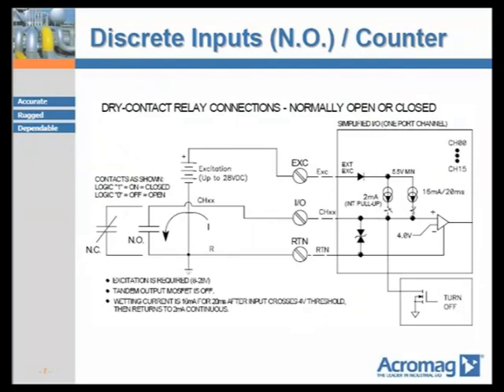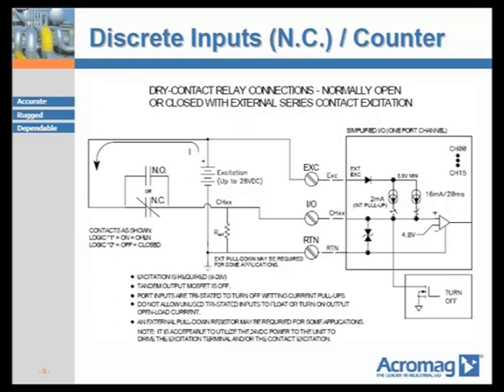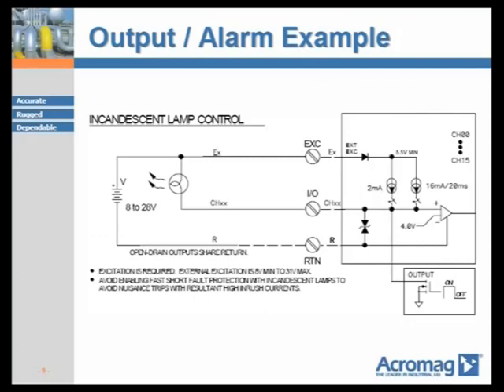This diagram shows the electrical connection to commonly used normally open dry contacts or proximity-type switches. The programmable wetting current sources act like pull-up resistors so the loop will not float in the event of a broken wire. A second diagram shows the electrical connection for normally closed dry contacts or proximity-type switches, where the 989EN offers programmable pull-down current sources so the loop will terminate to zero volts and not float. A third wiring example shows the 989EN solid-state FET output as a low-side switch controlling an incandescent lamp or LED indicator circuit.